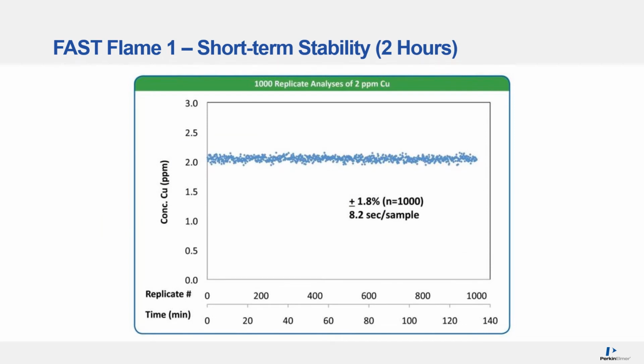If you're worried about the stability of such a high throughput system, let me put those worries to rest right now. Here's a short-term stability study where we analyzed 1,000 replicates of a 2 ppm copper solution. Our throughput here was about 8.2 seconds per sample. It took just over 2¼ hours to read these 1,000 samples, so it's a little over 2 hours. But the RSD for this entire run was only 1.8%. So very stable readings over that slightly longer than 2 hour run.